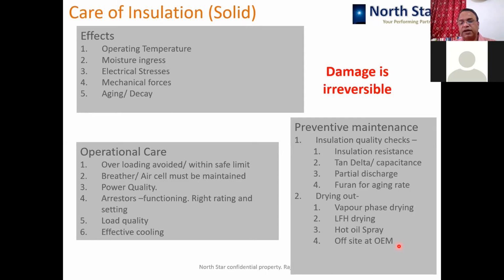So when the tan delta trend is continuously increasing, then maybe we can think about drying out the transformer using techniques like vapor phase drying, low frequency heating, hot oil spray, or taking the transformer from the site and sending it to the OEM for drying in the factory. So these techniques, these technologies and methods are to be adopted to dry the insulation.